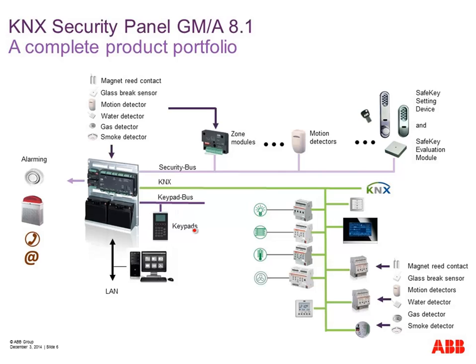The keypad bus is separated from the security bus to connect keypads used for operation and displaying status. Up to five keypads can be connected to one solution. The LAN Ethernet connection allows you to connect any PC via LAN cable or wireless LAN to completely program, commission, and also operate the solution and display status information. It's a very user-friendly, state-of-the-art solution. And last but not least, of course, KNX as a connection.